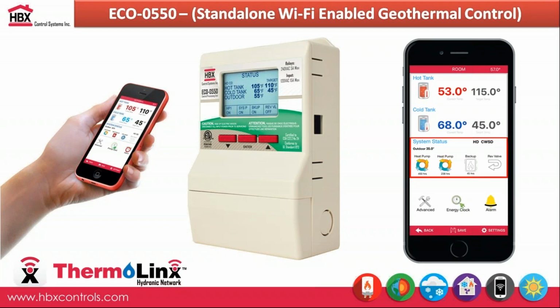So here you can see pretty much everything on the controller. You can see your hot tank and cold tank temperatures and targets. You can see what heat pumps and backup boilers are on or off, and whether your system pump is on. It will also give you the runtime cycles for those units as well. That's useful, because it could be telling you that we're short cycling the system, if you just installed it and you're getting maybe 1,000 stages after a week or so of runtime.